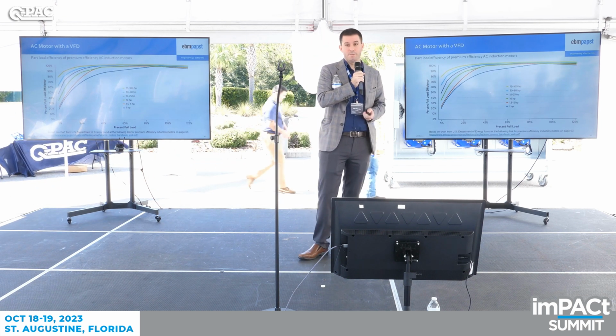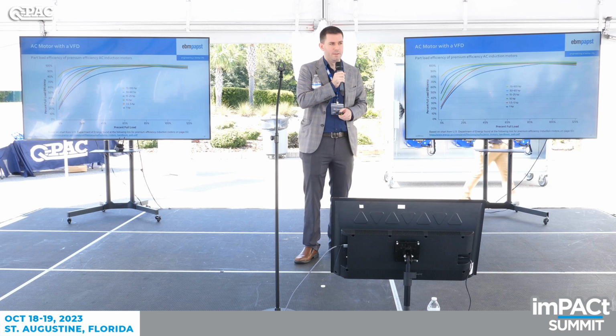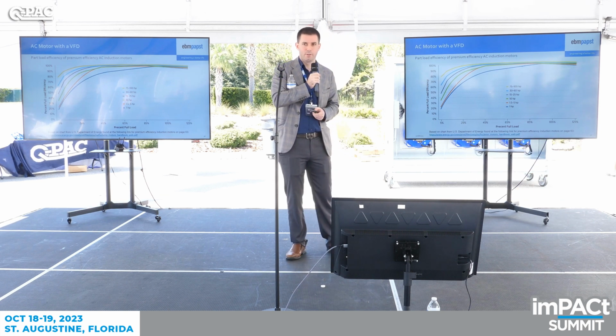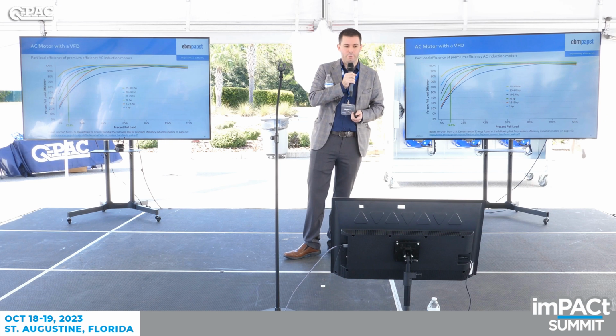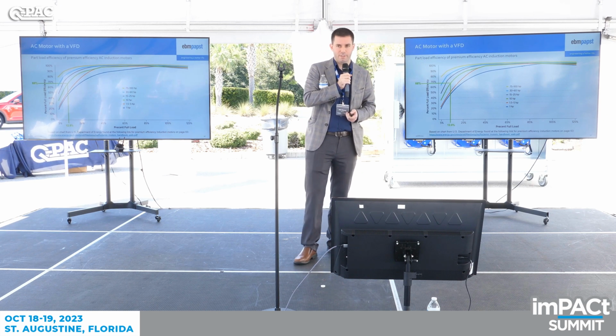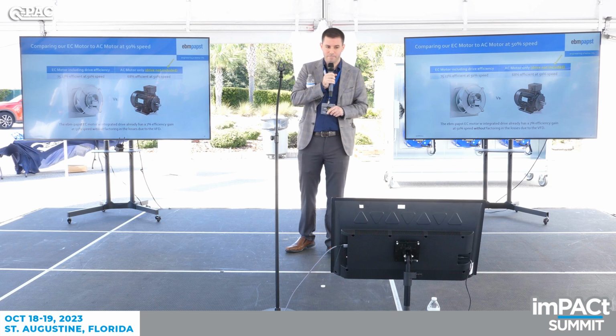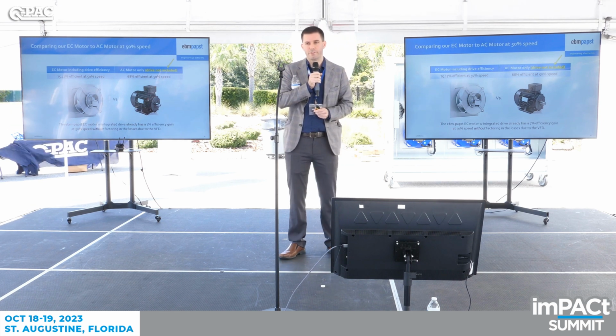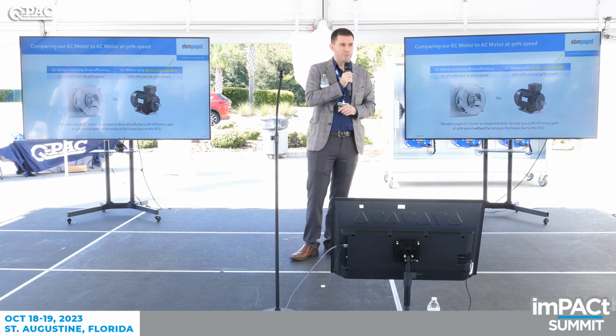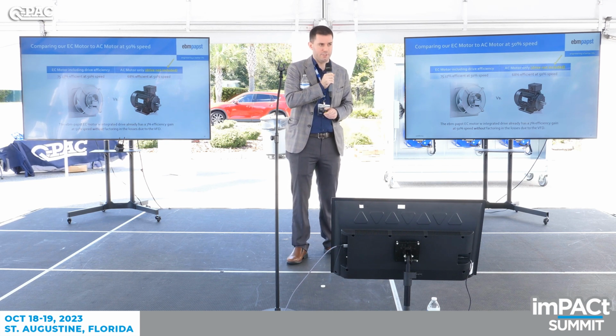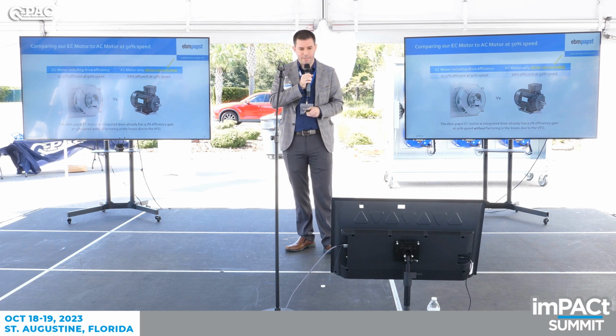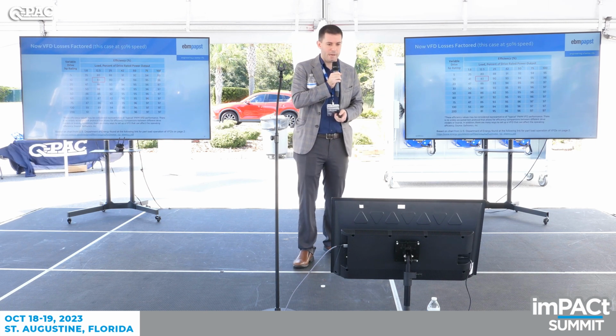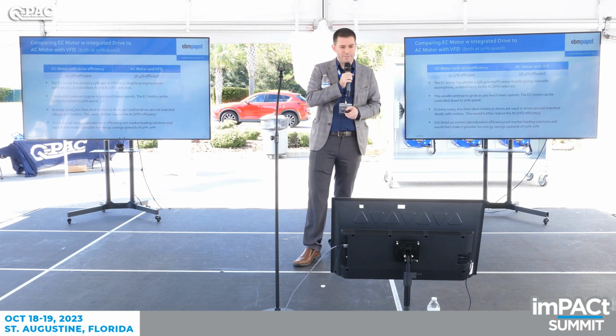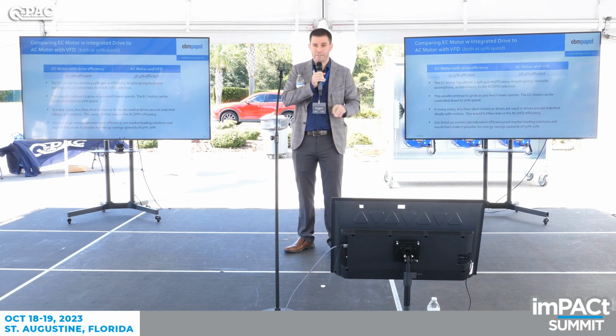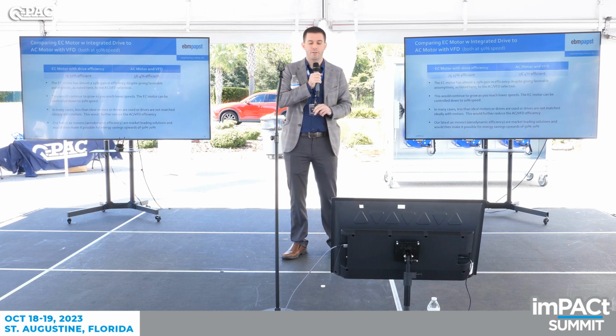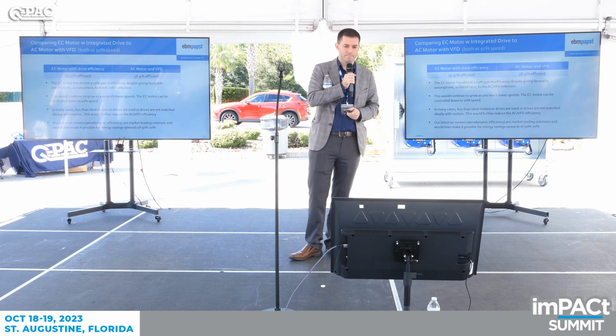So these are some energy.gov curves that I found on their website of how premium efficiency AC motors operate. So at 12.5% load, the 10 horsepower motor is 68% efficient. That does not include the drive. So we already have a 7% energy savings at 50% speed just based on pure motor technology alone. But now if we factor in the VFD and go to that 10 horsepower and 12.5% load, we're going to see the EC motor, just on motor technology alone at 50% speed, is gaining 19% energy efficiency.